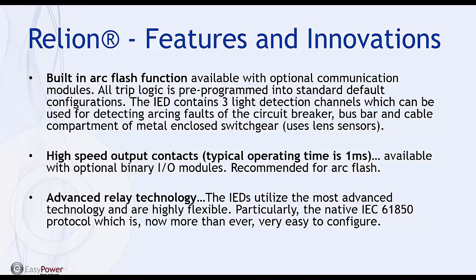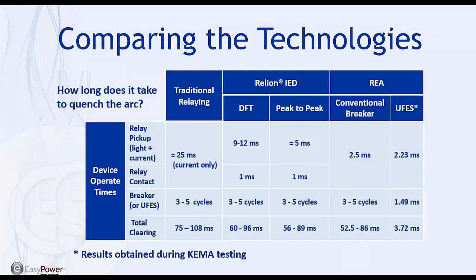Now we're going to compare the technologies. I've already done this to quite a degree, but just to get some numbers out there, you can see over here for traditional relaying, and this looks like it could be differential relaying, maybe a very fast instantaneous relay, 25 milliseconds. It's just current, not light. That's an order of magnitude of about a cycle slower. So if the arcing current's high enough, you can get into some danger. Like I stated before, we have instance 3 of our high stage protection that is 20 milliseconds. So if you have the high speed contact of 1 millisecond, then you're just under this 25 milliseconds. So even with our fastest technology, you're still a good cycle or more slower than the dedicated arc flash solutions. For ReliOn, you can see that now you're cutting this in half.